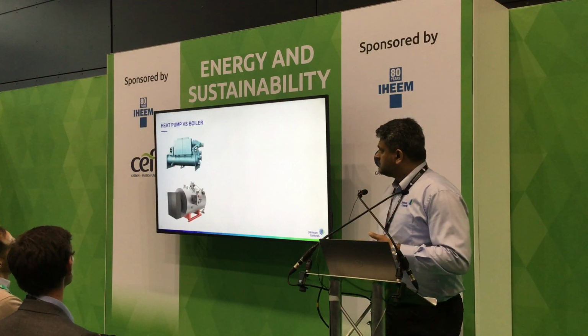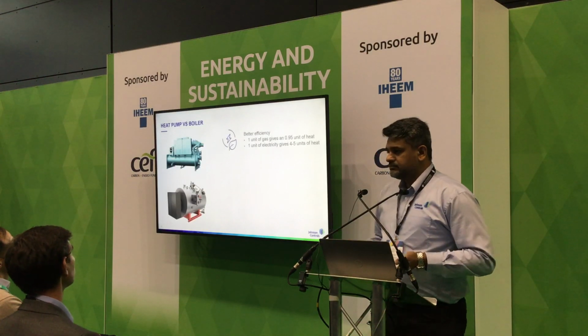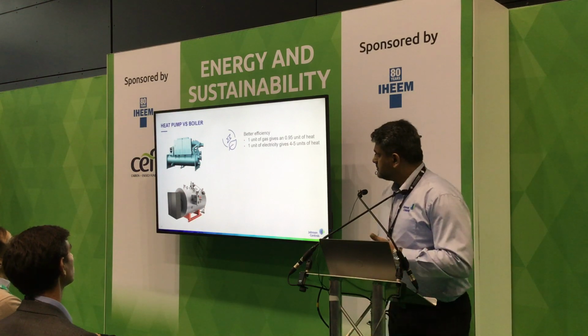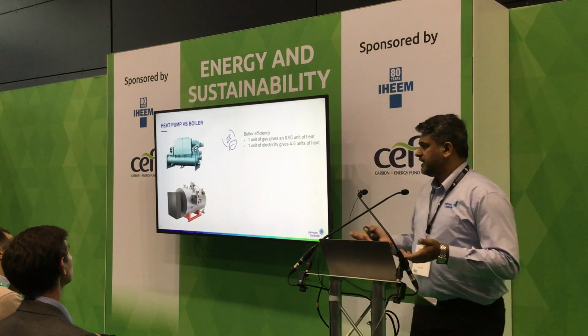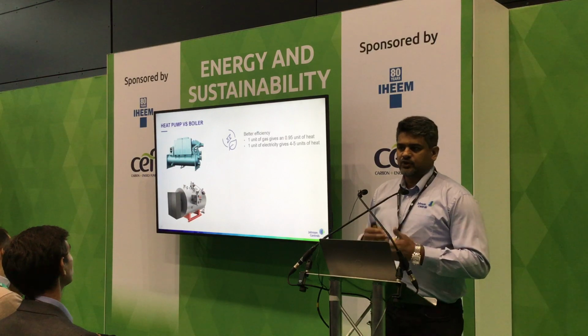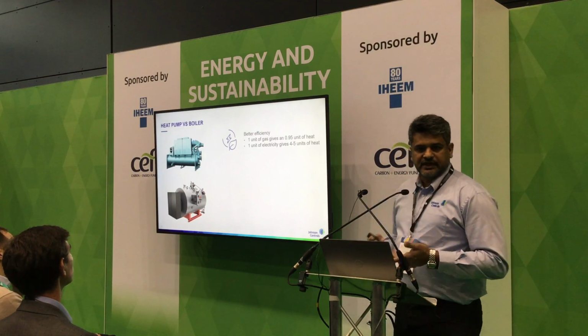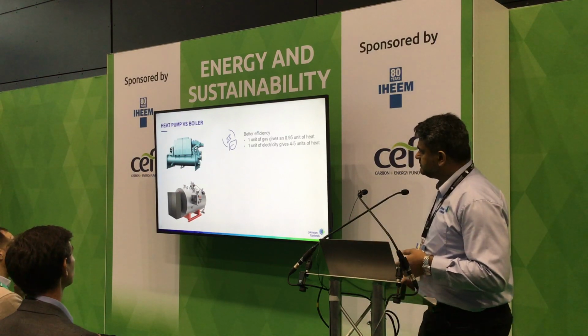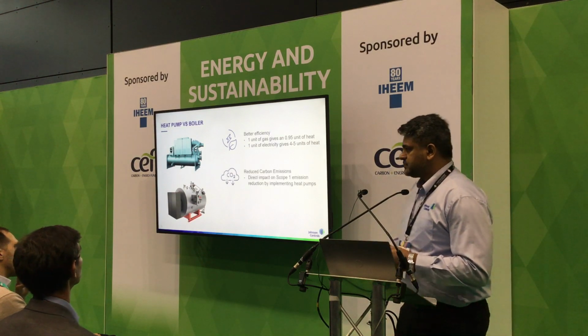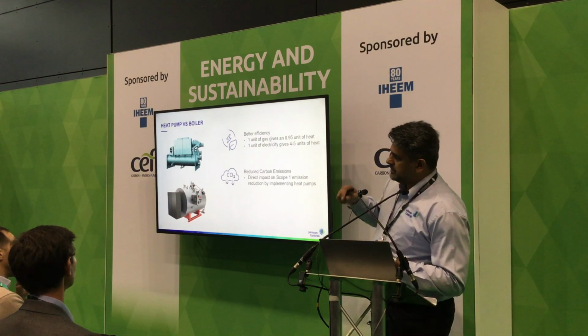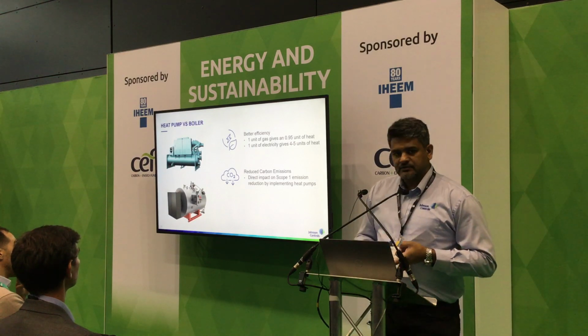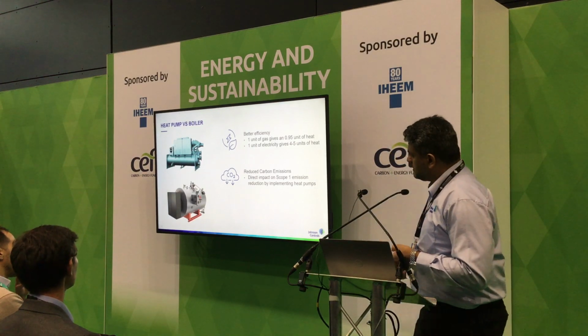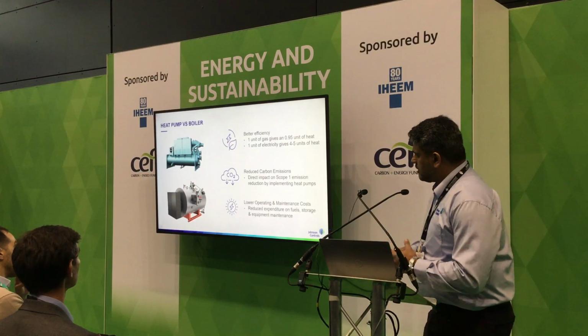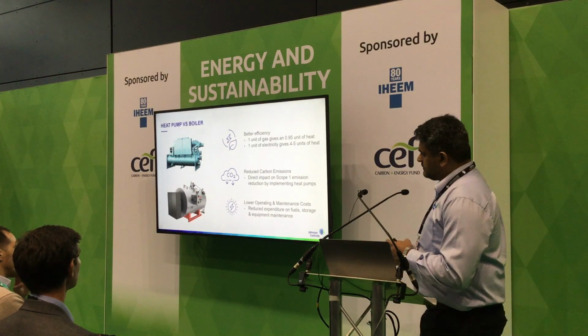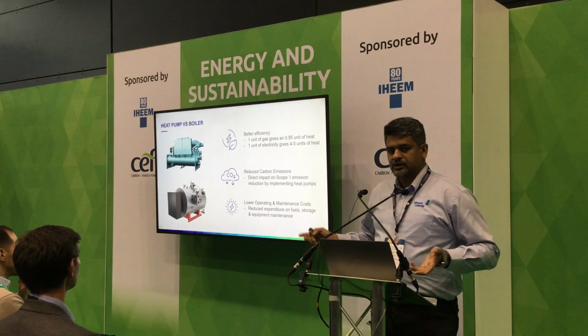Versus a boiler, obvious benefits. Most important, it's more efficient. A unit of gas would give you 0.95 units of heat, whereas you get about 4 to 5 units of heat from a unit of electricity that's pumped into the heat pump. Reduce carbon emissions, so it's a direct impact on scope 1, which is the facilities. And of course, lower operating and maintenance costs, so you have reduced expenditure on fuel, storage and equipment maintenance.